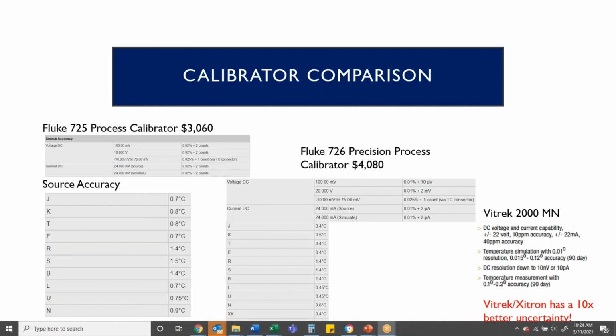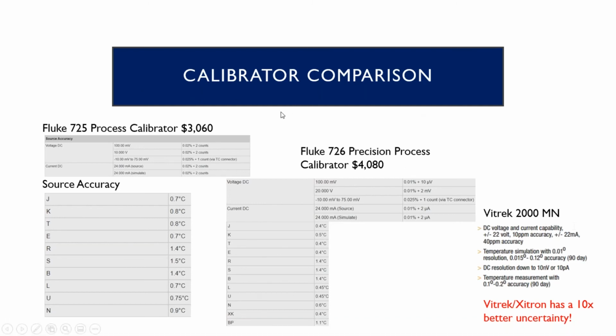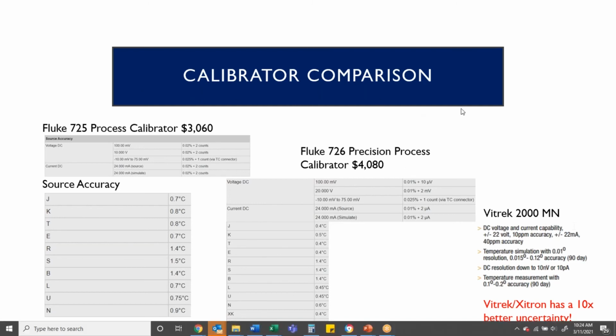Now, we're not as full-featured as the Fluke. The Fluke has an integrated meter and can do resistance. This calibrator is for a specific function, which is process cal on the floor and for checking to make sure your instrumentation is working. So we're not as full-featured, but what we do, we do a lot better, just to let you know.